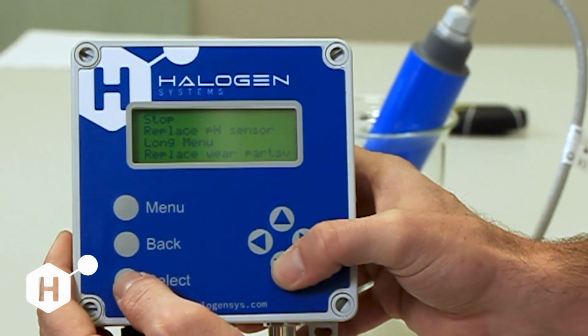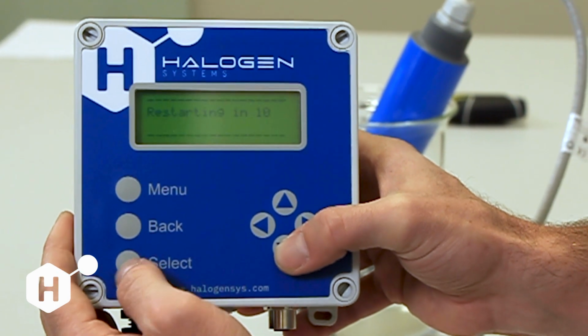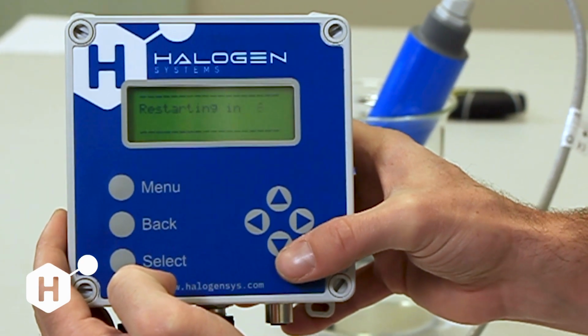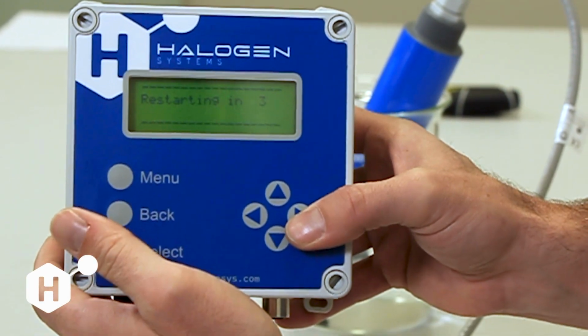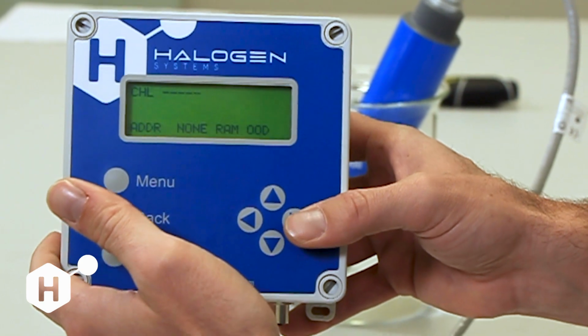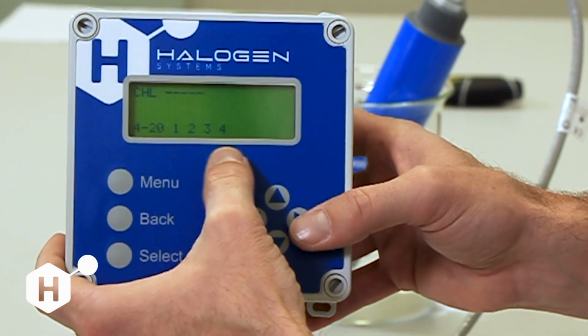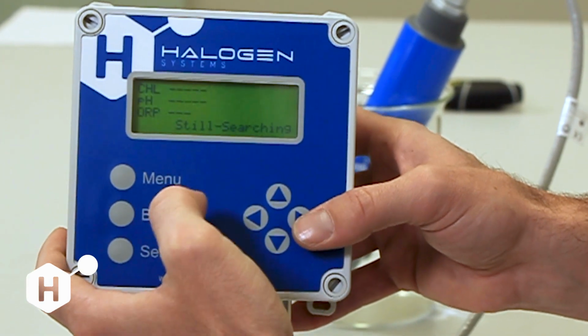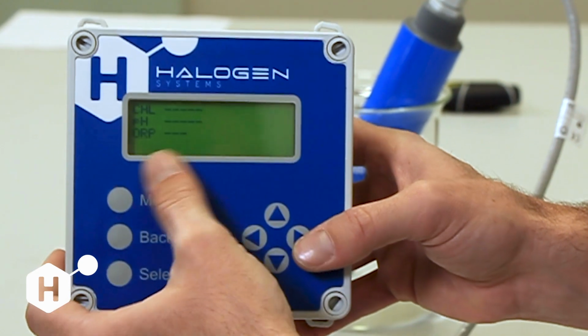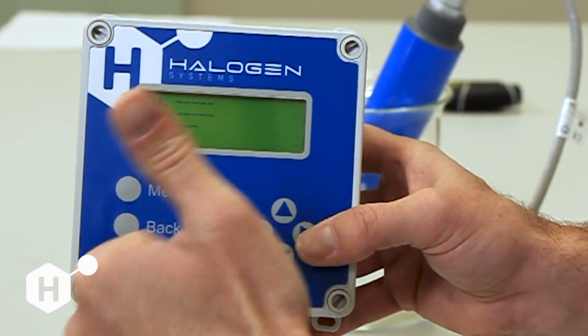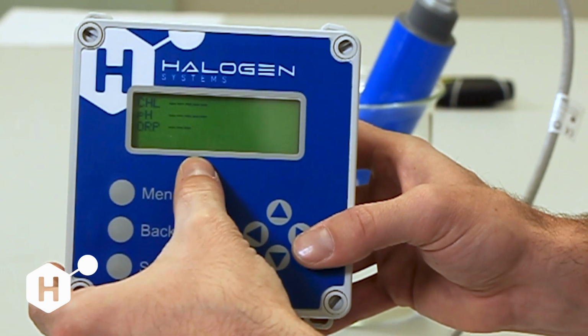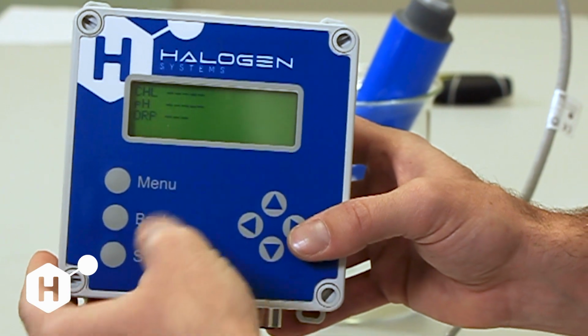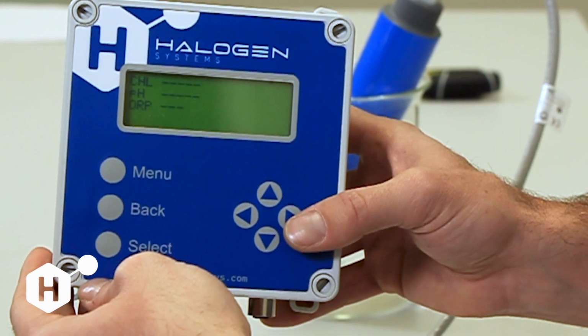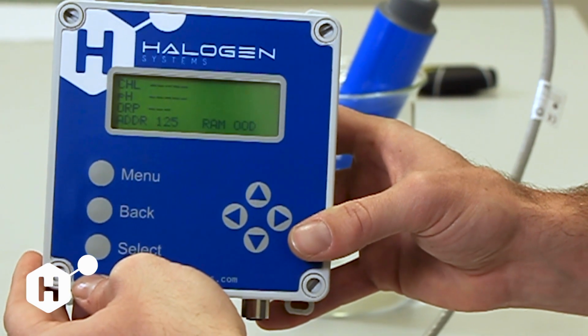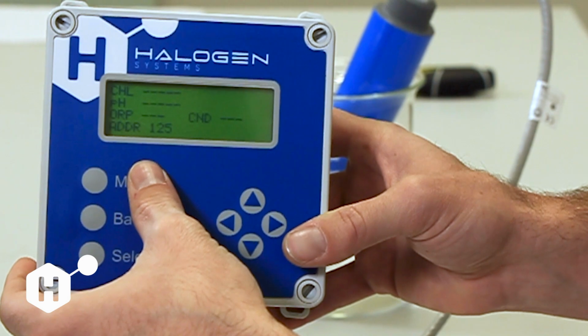The first thing I'll show you is how to do a system restart. We're going to hit menu, scroll down to maintenance, all the way down to the bottom of the maintenance menu, and hit restart system. It's going to give you a 10-second countdown, and this is going to restart the display for us. Once the display is restarted, it's going to run that bus search again and look for the sensor. The way we know we have communication here is we have the 4 to 20 outputs, 1, 2, 3, 4. We see searching, and if you don't get anything else here, this is good. That means you should shortly see address 125 pop up, and that's going to be your confirmation that we have established communication with this sensor at Modbus address 125. There you go. This is how we know that we have established communication with our sensor.